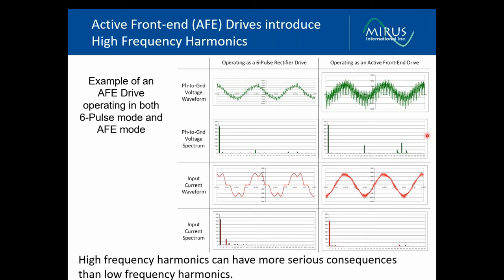So what we start with here is operating as a standard six-pulse drive, the phase-to-ground voltage waveform. We can see some high-frequency noise on that voltage waveform. But when we operate as an active front-end drive, the levels of high-frequency noise are much more severe. If we look at the spectrum of this waveform, we can see there are harmonic components at the higher frequencies, at much higher levels when operating as an active front-end drive.